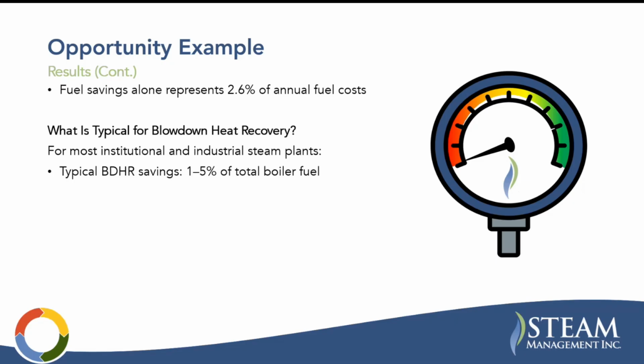I would say what is typical for a blowdown heat recovery system is probably about 1 to 5% of total boiler fuel. As we have seen, it is dependent on a variety of variables. So there's always kind of clues, but you always kind of got to run the numbers to make sure it works.